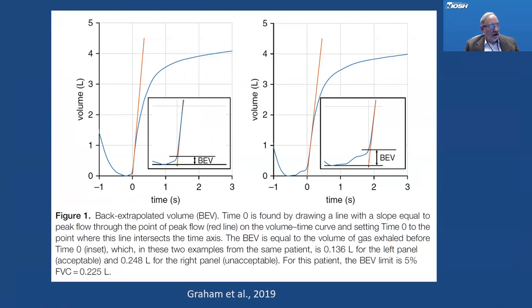Okay, so a little bit of expansion on this, back extrapolated volume. When someone blows hard from the very beginning, this is smaller than if they sort of lay into it. And here's an example of it.